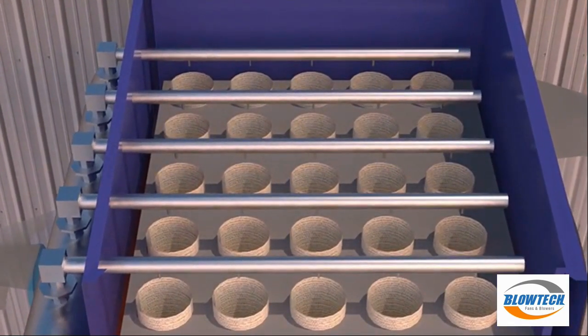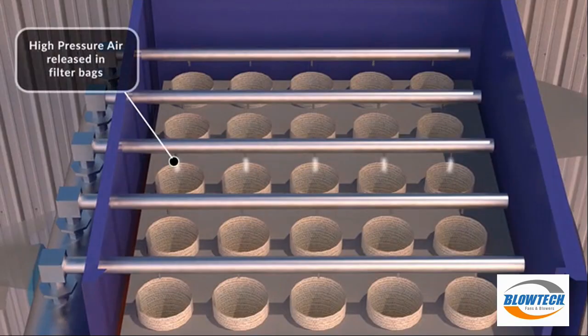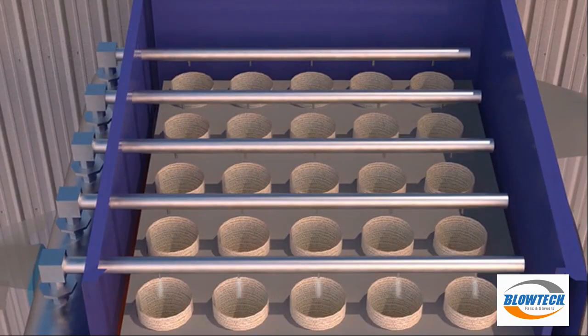This air passing through the filter bags releases the deposited dust and cleans the bags. The dust then falls off into the hopper. This process takes place at regular intervals of time, and this allows the filtration process to run smoothly.